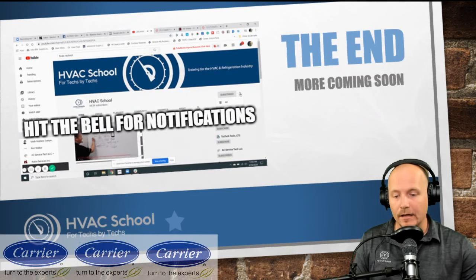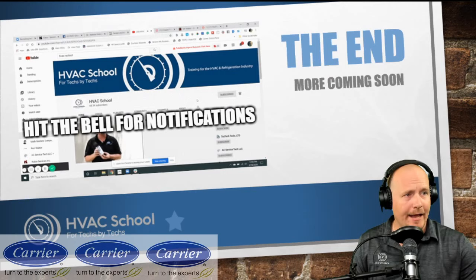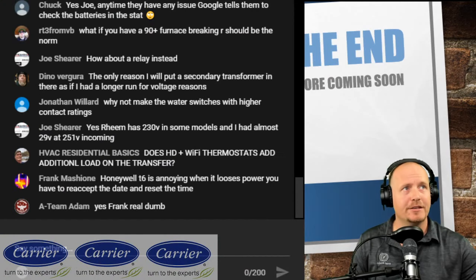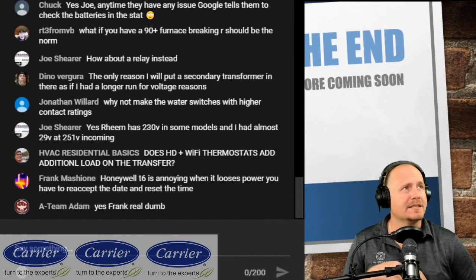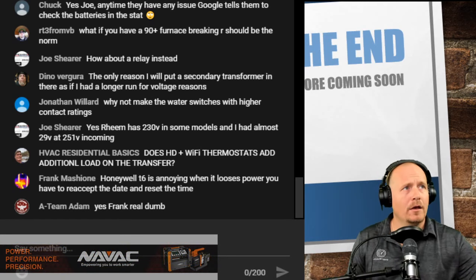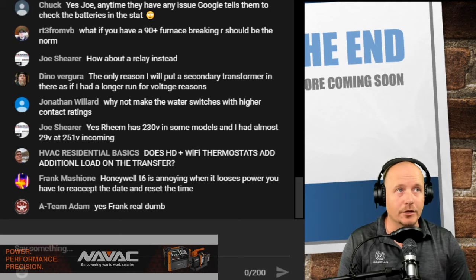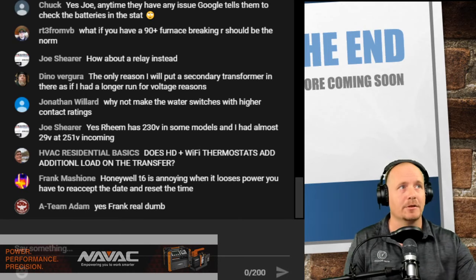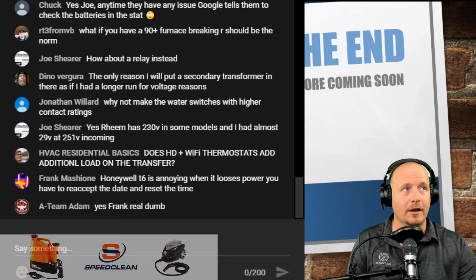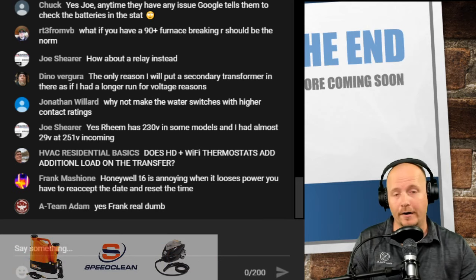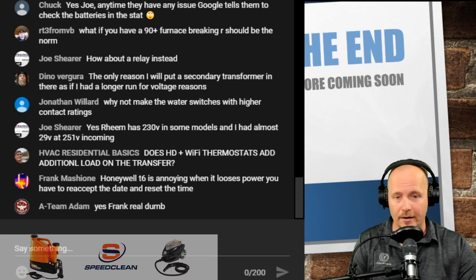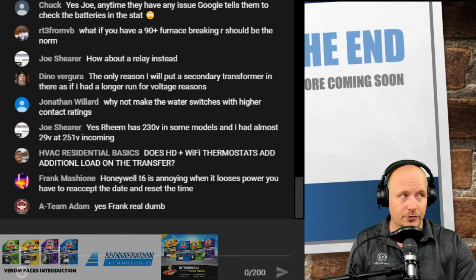Let's go ahead and open up chat, and I want to get your thoughts. You guys have been chatting. Let's see here. What if you have a 90-plus furnace? Breaking R should be the norm. Yes, that's a good point. I don't usually think in terms of 90-plus furnaces, but yes, if you have condensate coming off of the furnace itself, then you definitely need to break R, and breaking R is my standard way of doing it anyway. So yes, that's definitely true.